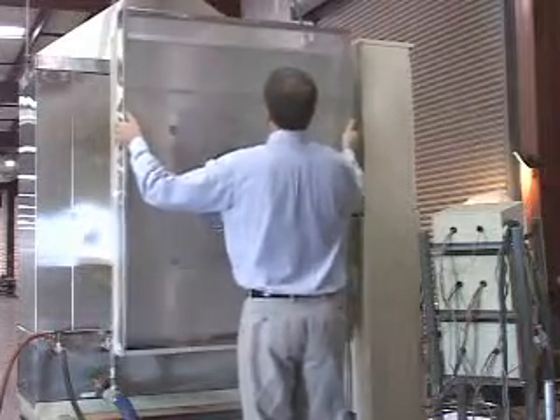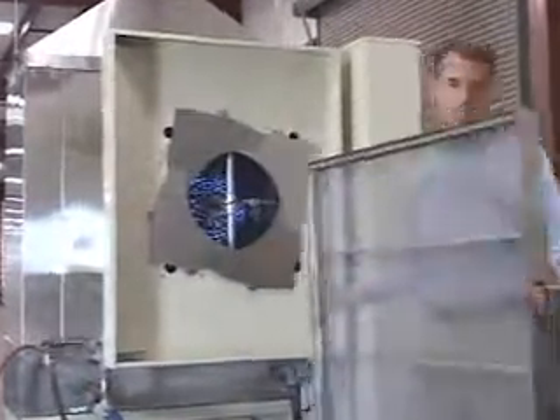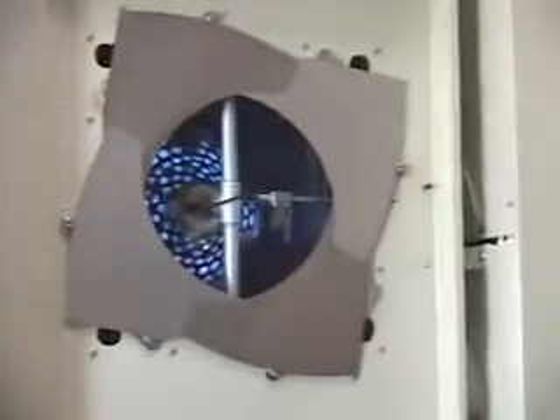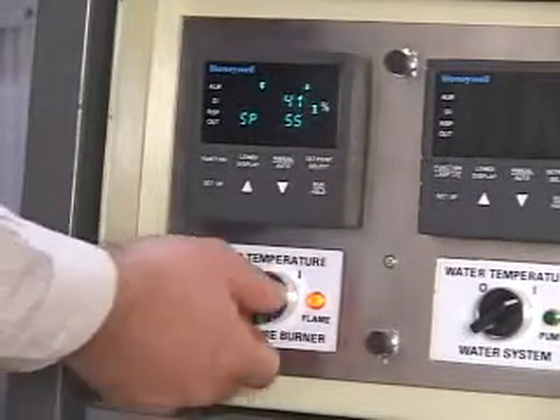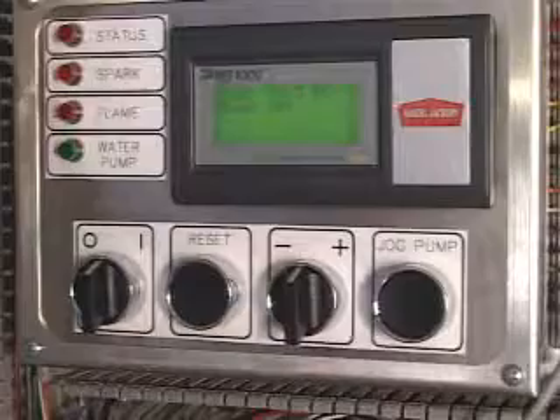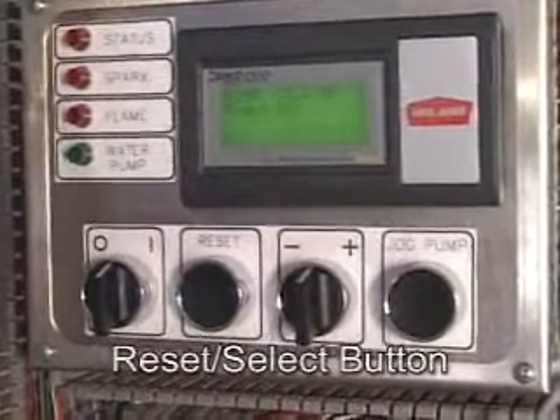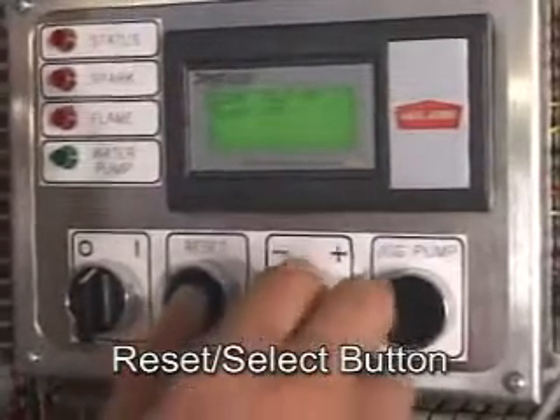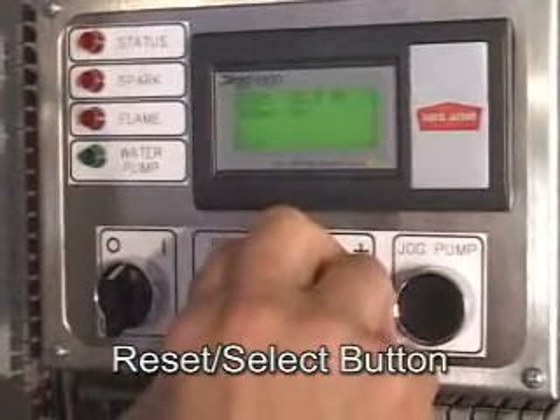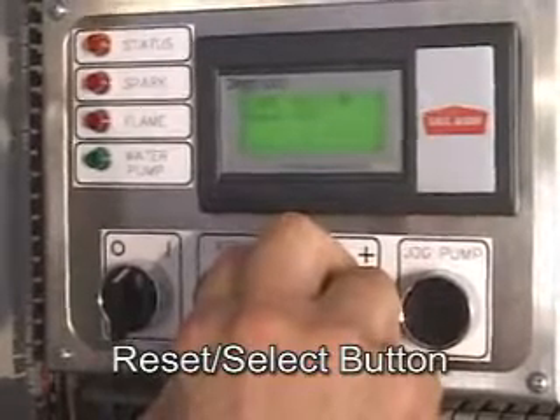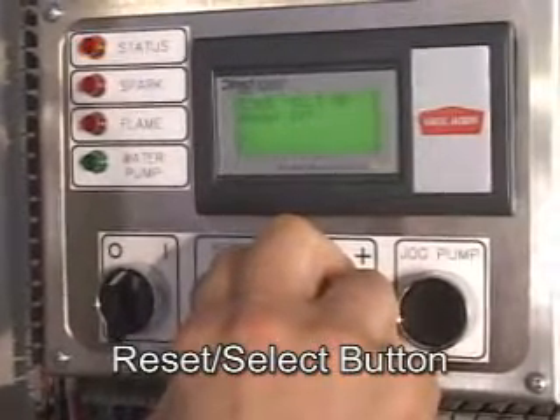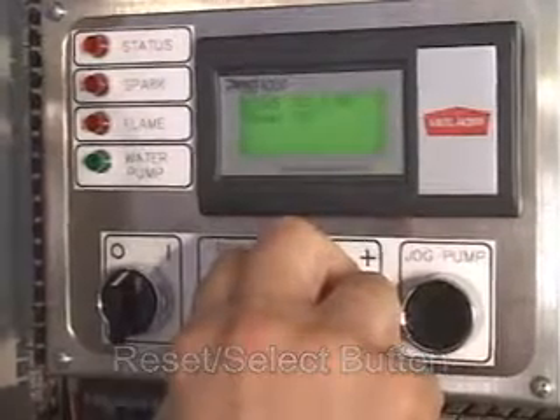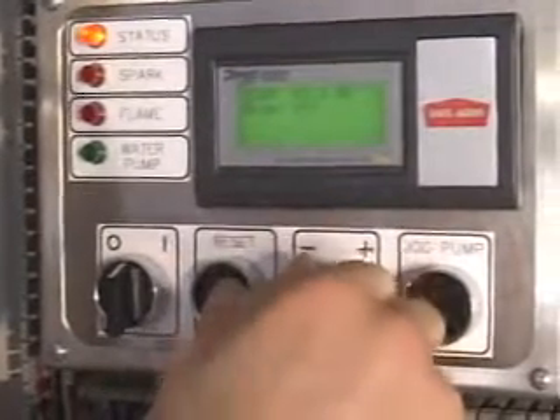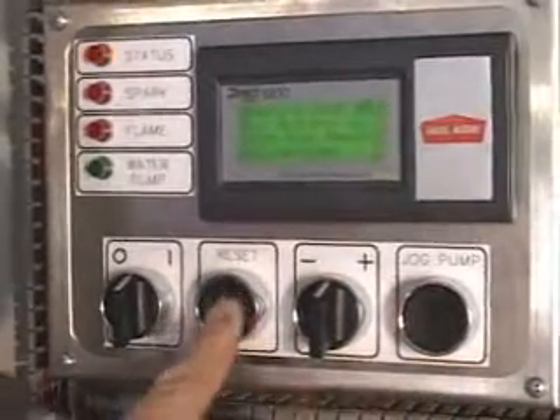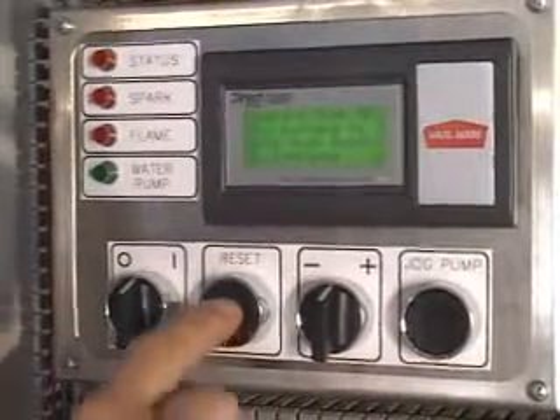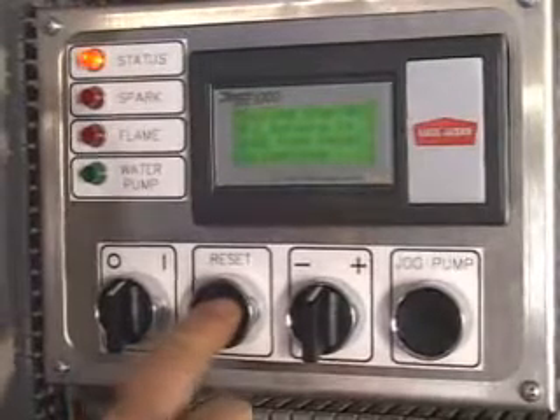A comprehensive test and diagnostic program can be activated to assist with technical adjustments and troubleshooting. To enter this program, the unit must be turned off, but power must be on. While pushing the select button with the left hand, turn the plus-minus switch to the left. The status light will flash to signal the passing of 5 seconds. While continuing to hold the select button, release the plus-minus switch and turn it to the right momentarily. The status light will now flash to indicate that the unit is in testing mode, and the LCD display will offer details relating to the step.